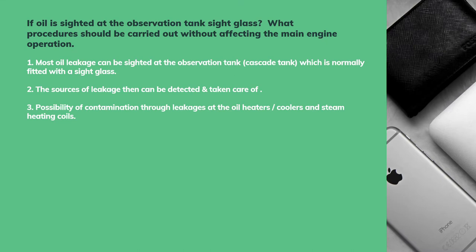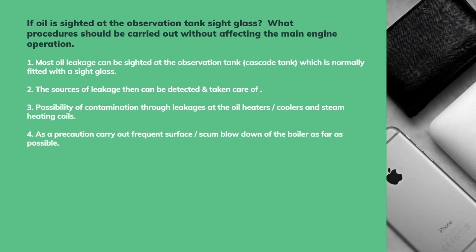The possibility of contamination is through leakages at the oil heaters, coolers, and steam heating coils. As a precaution, carry out frequent surface or scum blowdown of the boiler as far as possible. These leakages can lead to foaming, priming, and carry-over.